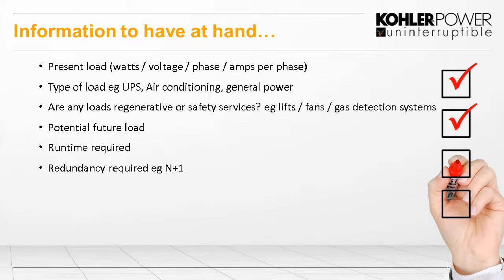So once you've decided you want a generator, we're going to have some information to hand when you go to a supplier. We want to know what loads you have. Very important, we need to understand what load it is, what type of load it is, UPS, general power. Are any of the loads safety services or regenerative load? Because that will make a difference in how we select things. And of course, we need to understand if it's just like the critical load and non-essential load, what do we want to do? And are we planning on changing that load requirement in the future?